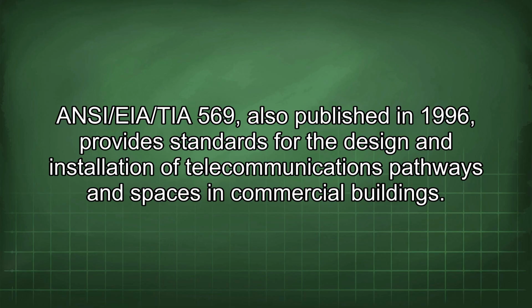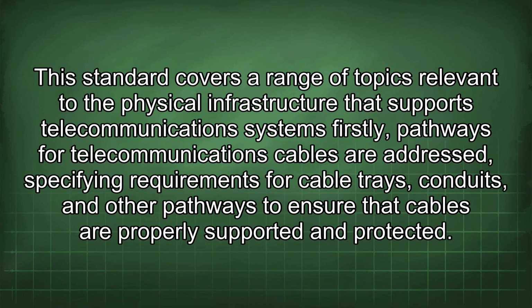ANSI/EIA/TIA 569, also published in 1996, provides standards for the design and installation of telecommunications pathways and spaces in commercial buildings. This standard covers a range of topics relevant to the physical infrastructure that supports telecommunications systems. Firstly, pathways for telecommunications cables are addressed, specifying requirements for cable trays, conduits, and other pathways to ensure that cables are properly supported and protected.